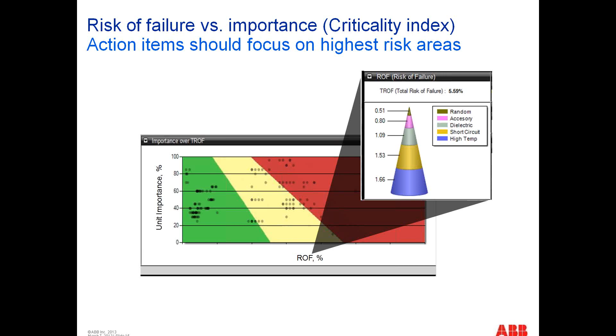So to summarize, step 1 is a broad fleet screen that identifies the transformers - the gray box is the unknown ones. Once we take a look at some data on the transformer, how it's been performing for you, some conditional information, oil samples, power factor and capacitance tests, that sort of thing, then we can start coloring those transformers either red, yellow, or green.